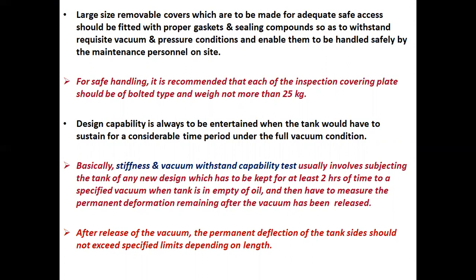For safe handling, it is recommended that each of the inspection cover plates should be of bolted type and weigh not more than 25 kg. Design capability is always to be considered when the tank would have to sustain for a considerable time period under the full vacuum condition. Basically, the stiffness and vacuum withstand capability test usually involves subjecting the tank of any new design, which has to be kept for at least 2 hours, to a specified vacuum when the tank is empty of oil, and then measuring the permanent deformation remaining after the vacuum has been released. After release of the vacuum, the permanent deflection of the tank sides should not exceed specified limits depending on length.